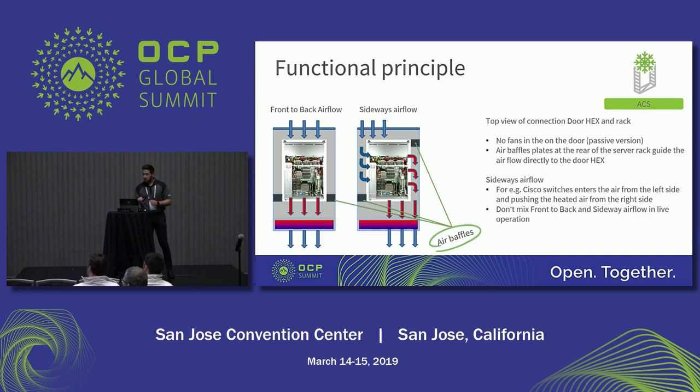One important thing is that it is not recommended from our side to mix up these two systems, front-to-back and sideways. Also, as I mentioned previously, what I'm showing here is a passive version. That means there are no fans installed on the rack. The fans are installed on the server.